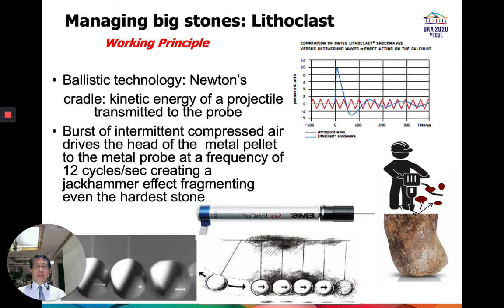The pneumatic system of the Lithoclast is based on Newton's cradle: the kinetic energy of a projectile propelled by a burst of compressed air against the head of a metal probe at a frequency of 12 cycles per second. This is responsible for breaking up the stone once the tip of the probe comes in contact with it, very similar to what a jackhammer does.